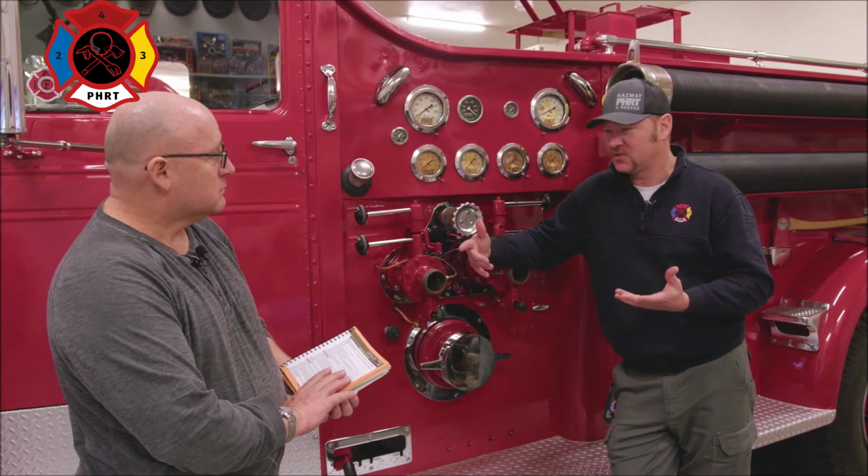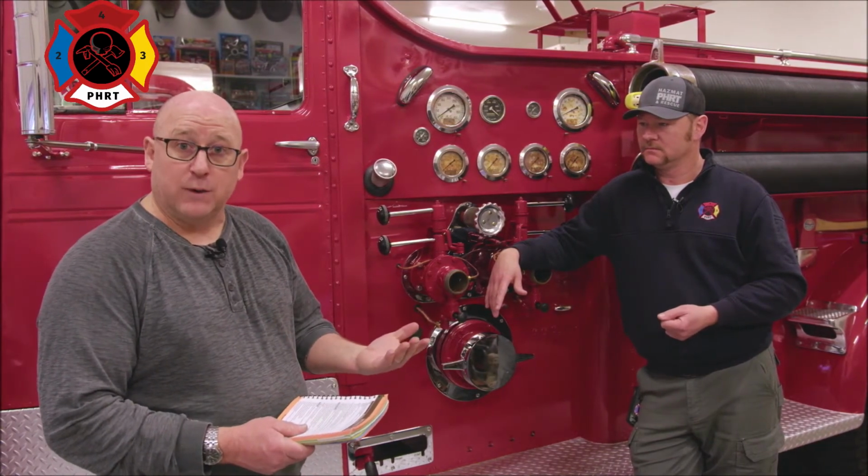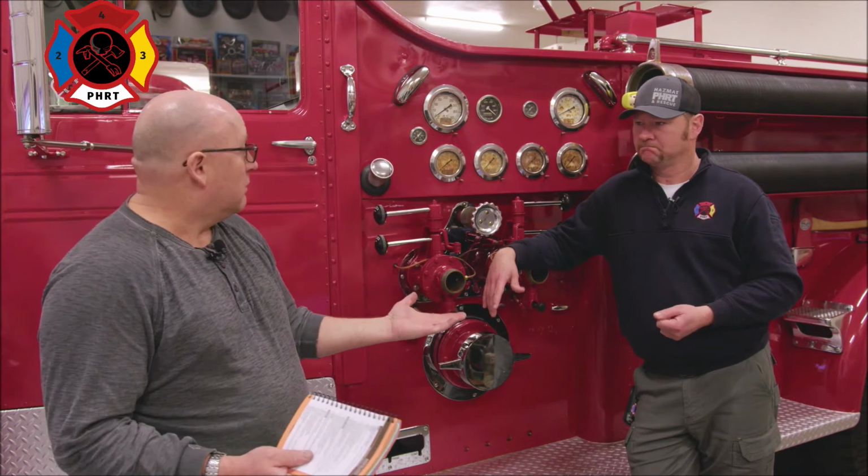Got it. What about light switches or garage door openers or anything like that? Is that a big enough ignition source to light these things off? It actually is. That's a great question. Even turning a light off creates a spark that, if there is a flammable atmosphere around it, will cause an explosion. Turning the lights on or off, or even something as seemingly beneficial as pulling the smoke detector or the pull station to activate the building's fire alarm, could cause a spark that could catch an entire motel on fire, for example, and cause an explosion.